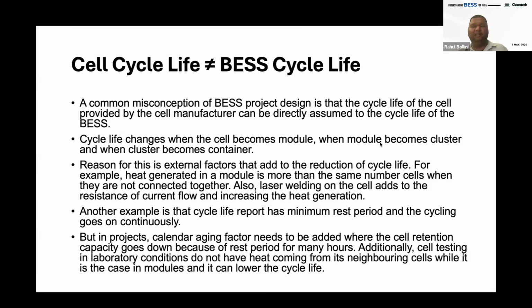But the good thing about the BESS is you could take a BESS to 60% SOH. You have that leeway. And cell cycle life, typically people do at 70%. But one must be very careful after the 70% degradation. The degradation from 70 to 60 may not be even. Nobody has seen it. And looking at my past experience of cell degradation curves, I can tell you there can be a knee point. I've written an article about it, but knee point is, like I said, there's a flat degradation, and the knee point is a point where it bends down. So it's a very high possibility. So you need to be prepared for risk mitigation in projects where you're going below 70, or typically below 65. Okay, let's go to the next topic.